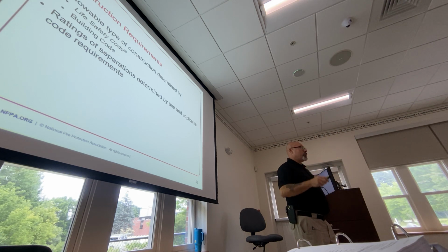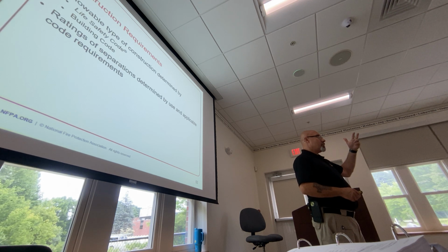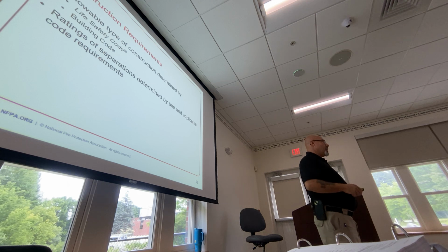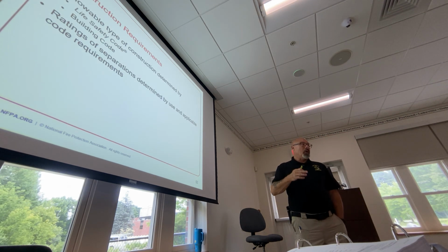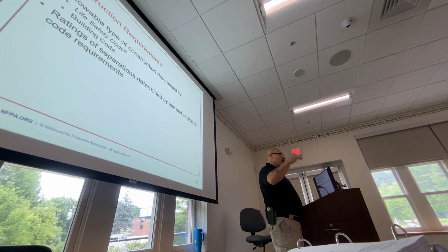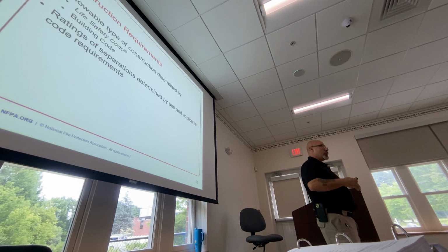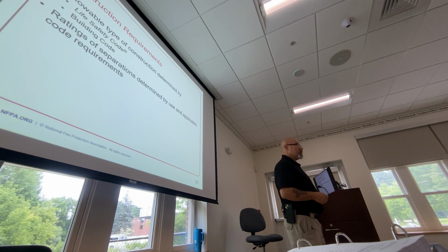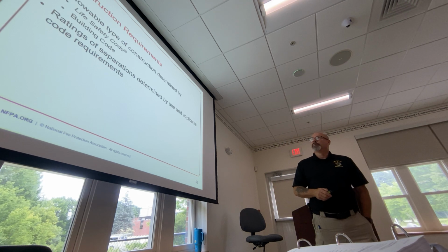My checklist that I provide all of my staff when they first start: first thing, what kind of occupancy do we have? Figure that out. What kind of construction type do we have? And then how many stories are there? From there, once we get the construction type, table 1.6 in every occupancy chapter that is applicable is gonna tell us whether they can or cannot do what they're trying to do. We'll practice that. We'll go down through, do a few things.